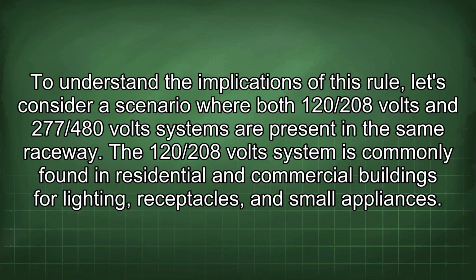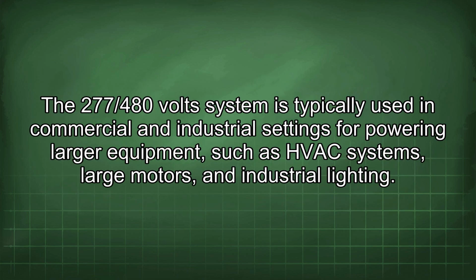To understand the implications of this rule, let's consider a scenario where both 120/208 volts and 277/480 volts systems are present in the same raceway. The 120/208 volt system is commonly found in residential and commercial buildings for lighting, receptacles, and small appliances. The 277/480 volt system is typically used in commercial and industrial settings for powering larger equipment, such as HVAC systems, large motors, and industrial lighting.